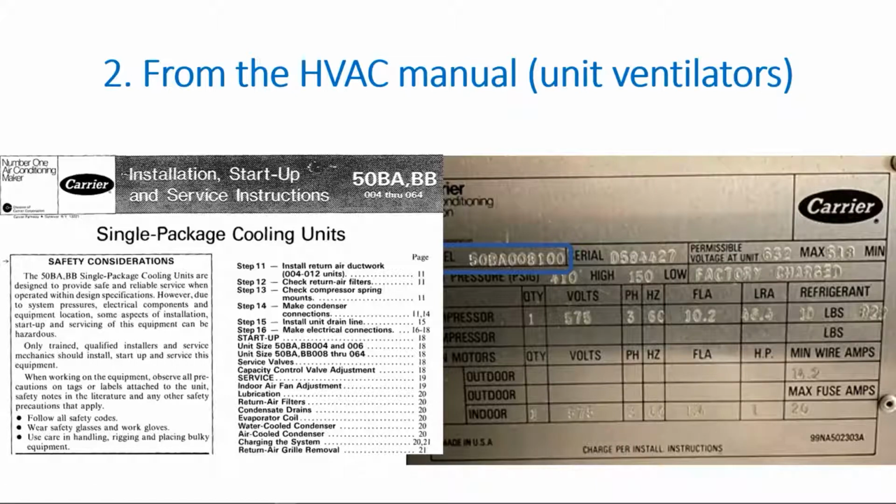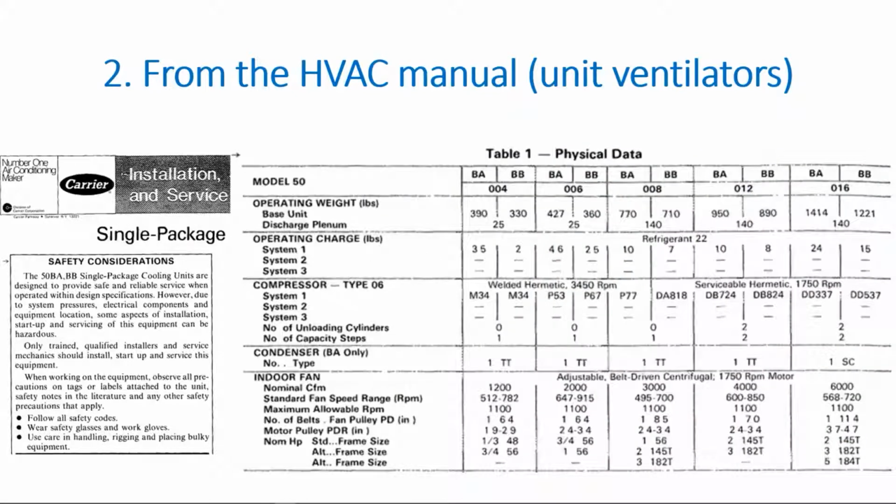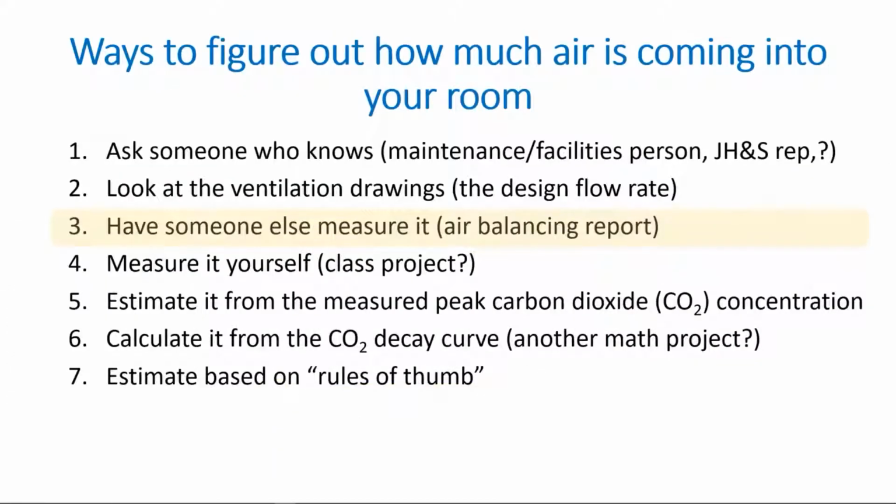Normally, these things have a life expectancy of 15 to 20 years, so you can imagine how I feel about this. And in the manual, I found our model, and it has nominal cubic feet per minute of 3,000 CFM. And so that's another way of finding out. Have someone else measure it for you.